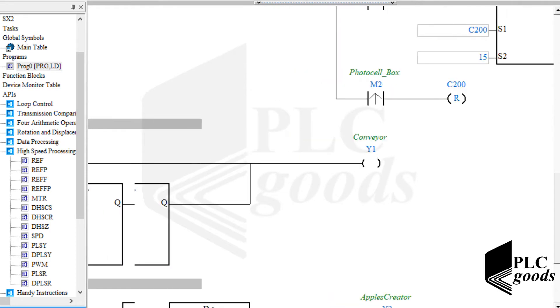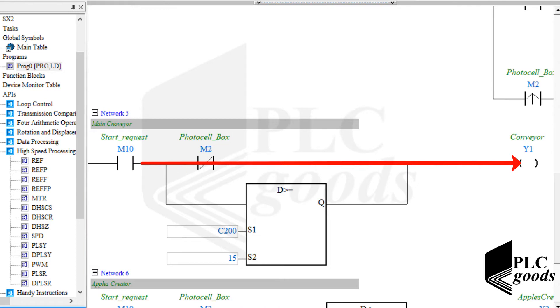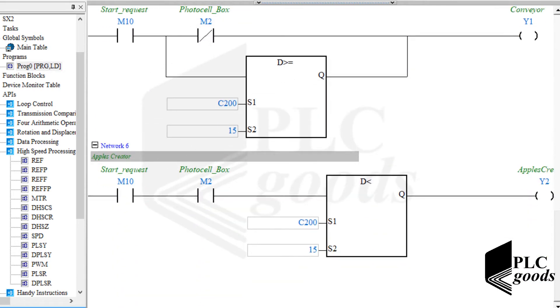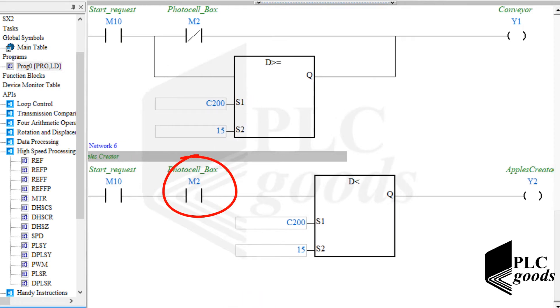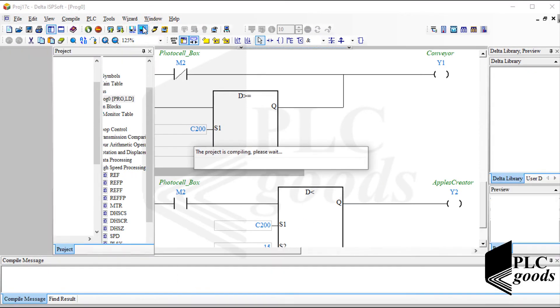The next network determines when the conveyor must be on. Naturally, if the start request is enabled, the conveyor must be on — except when it reaches in front of the apples creator system. After that, when 15 apples are put in the box, the conveyor must be turned on again. Finally, the last network determines when the apples creator system must be on: if the start request memory is enabled, there is a box in front of the system, and the number of apples passed into the box is less than 15. Now let me download the program to my PLC.